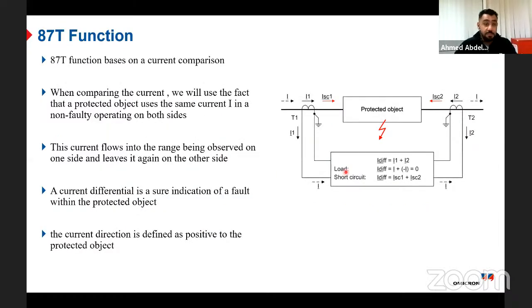The differential protection function is very important and very simple, but it needs some awareness. It is based on current comparison, because we have all studied Kirchhoff's current law, KCL, which says that the summation of all currents in and out of any electrical node should equal 0 in a stable condition, or in healthy operation. In other words, all current in should equal all current out, taking the vectorial direction into consideration. What does vectorial direction mean? I need to assume a reference direction going into the node, which is positive, and the current leaving the node should be negative. Hence I can sum all currents, and if my system is stable or healthy, the summation equals 0.